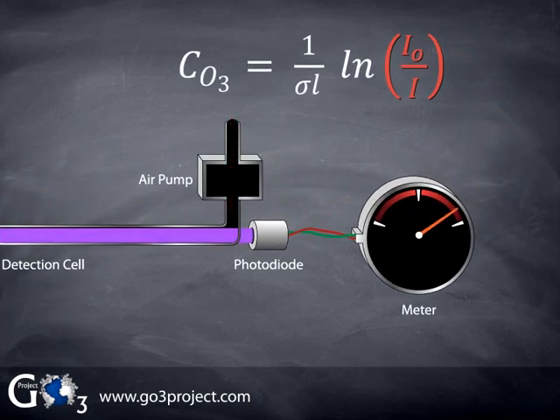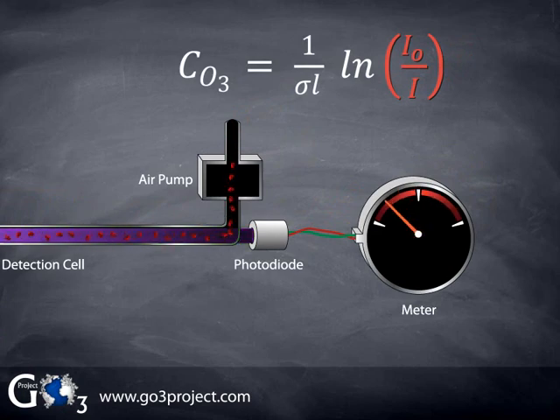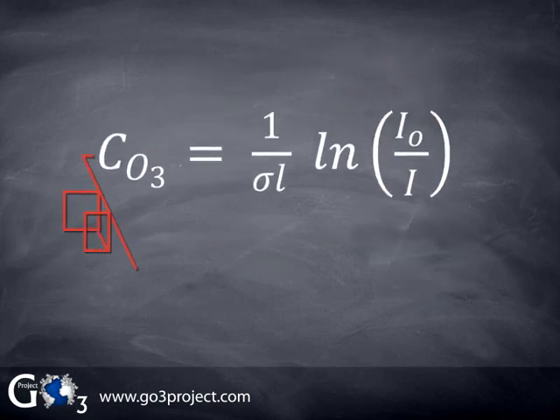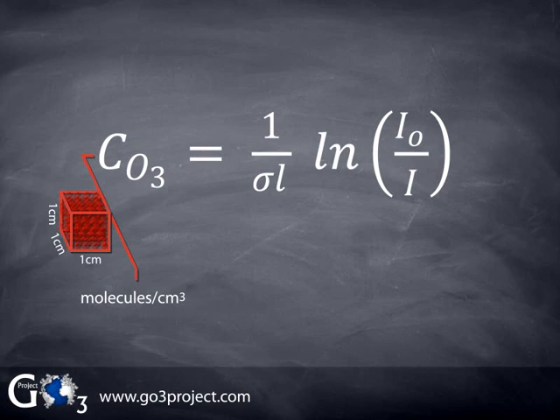We could calculate an updated ozone concentration each time we measure a new value of either I0 or I, which is every 2 seconds. However, most applications don't require such a fast response time. Let's take a moment to examine the units of our calculation. The concentration of ozone is expressed in molecules per centimeter cubed. The units result because the units of the absorption cross-section are centimeters squared per molecule, and the units of path length are centimeters.